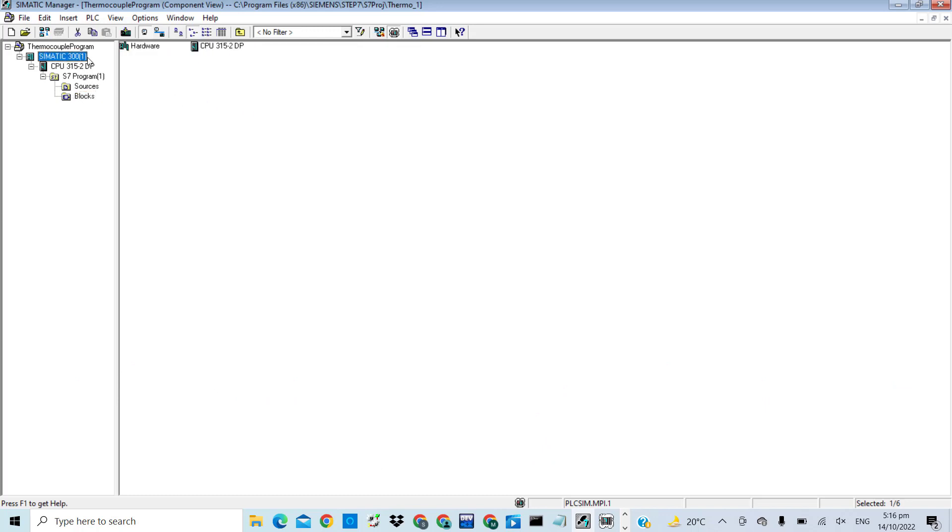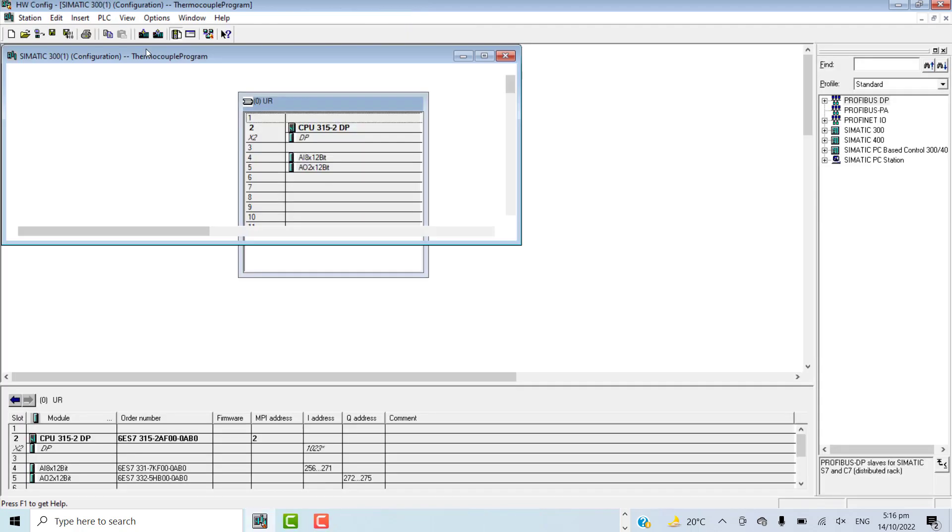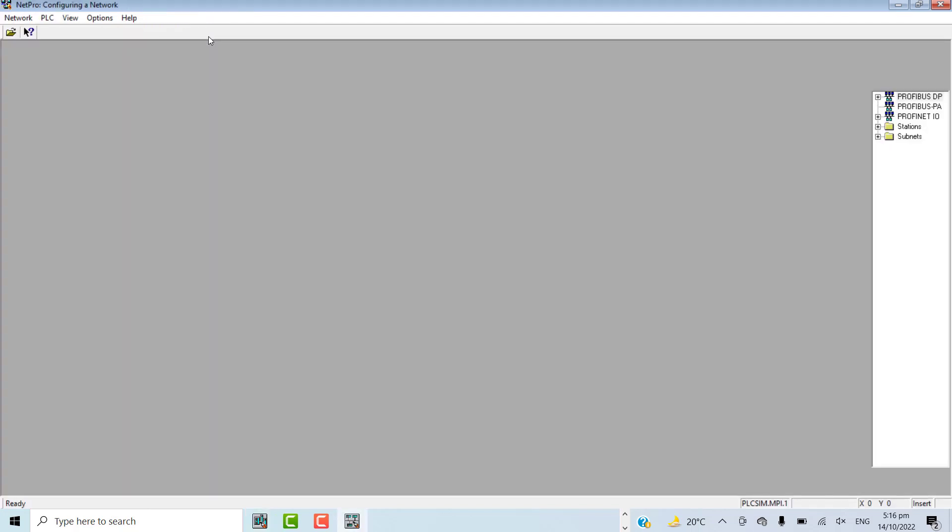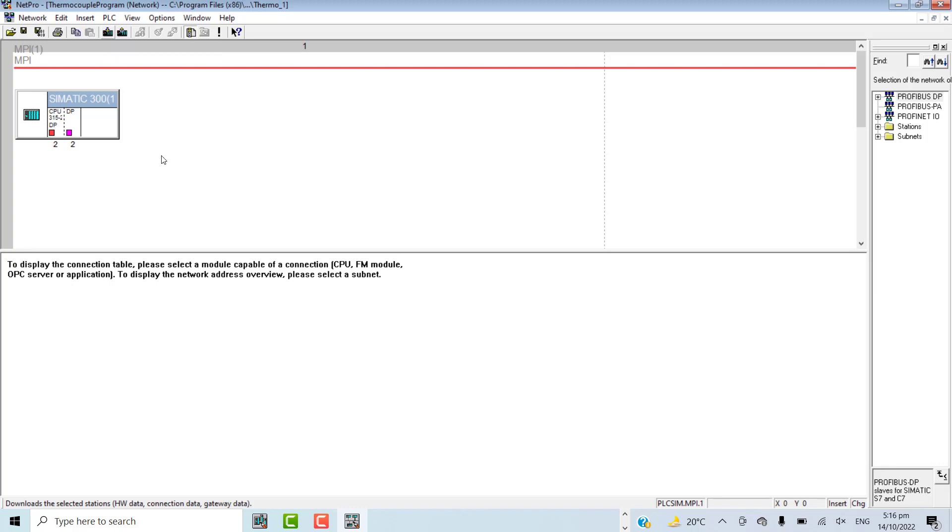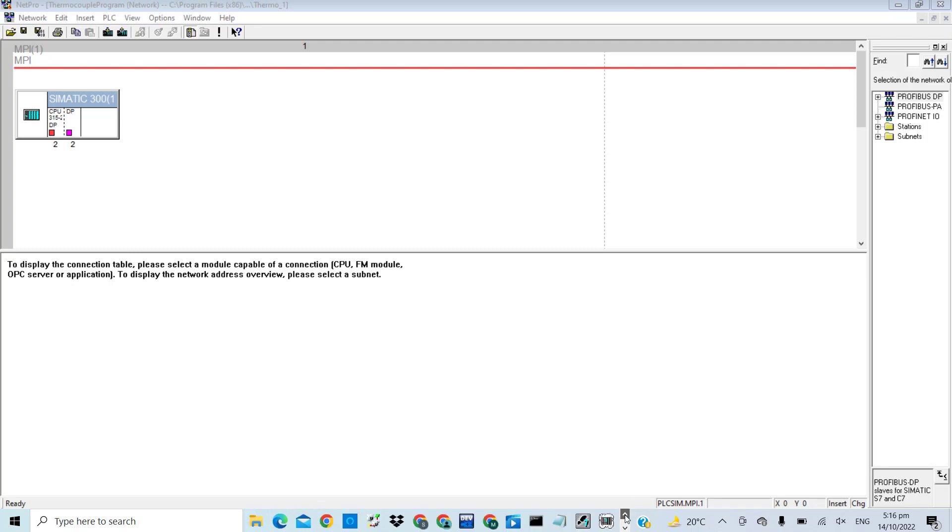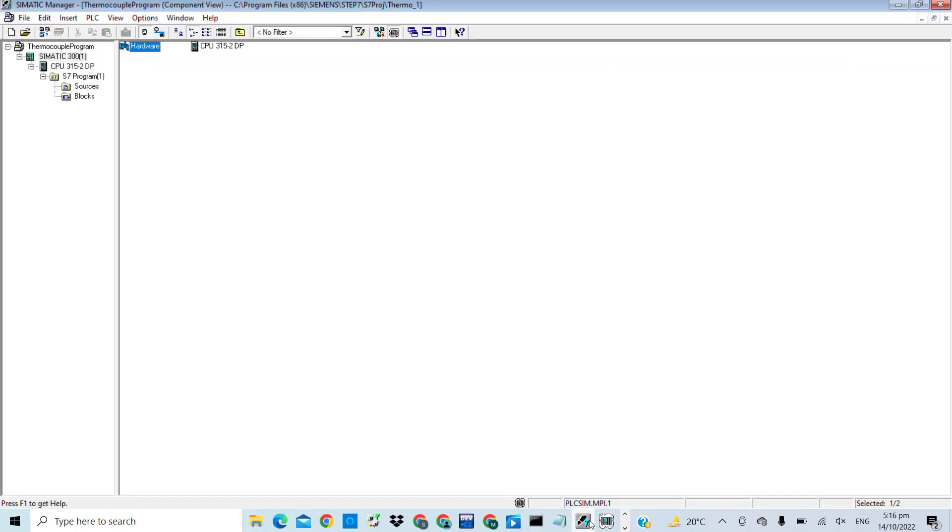First, you will download the hardware configuration entirely. Then you will download the network configuration in its entirety. And last, you will go for the CFC logic or ladder logic and try to download the entire logic as well to the CPU.